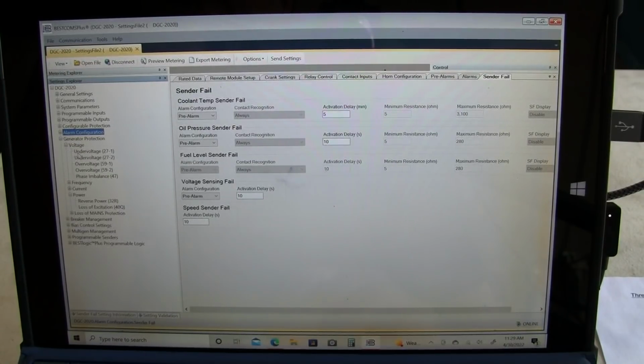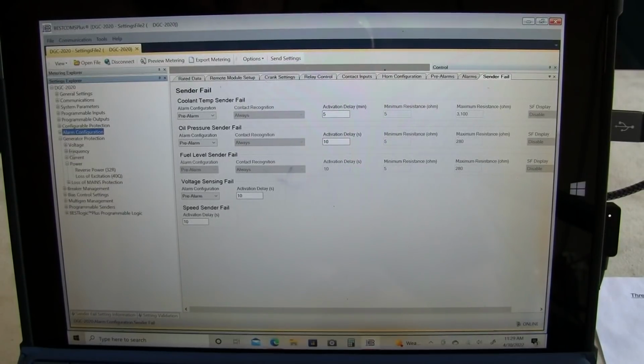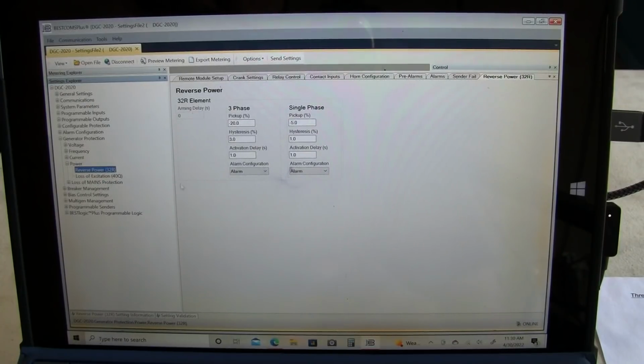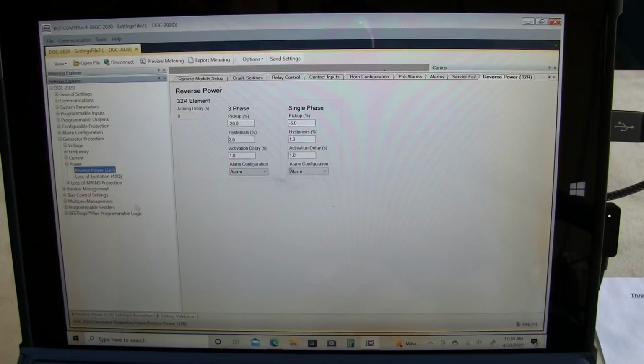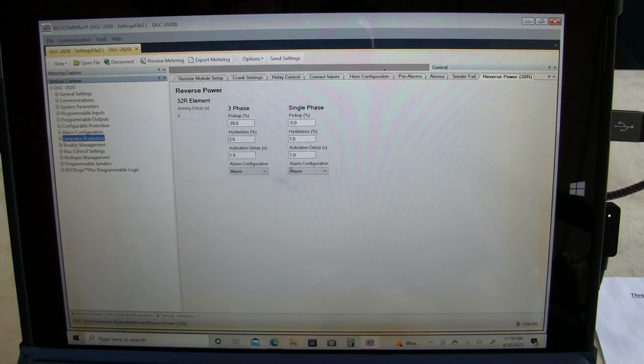Voltage. We got under voltage, over voltage. Now you see we got 2 under voltage and 2 over voltage. This is typically used, you use the second under voltage. If you had a multi-voltage unit, you would have an under voltage and an over voltage setting for either its high voltage connection or its low voltage connection. Same thing for frequency, current, power, reverse power. We always enable that. That's just in case, for whatever reason, while the genset's running, something starts backfeeding it, it'll shut the engine down. Breaker management we don't have to worry about. Multi-gen management we don't have to worry about.